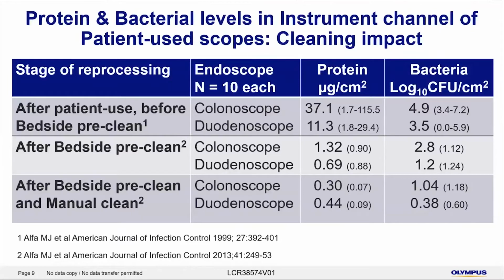What I'd like to point out is the second row, which is after the bedside pre-clean. In all instances, you're getting over 94% reduction in the protein levels, and you're getting at least a 2 log reduction in the microbial levels. So you can see that it's an ideal opportunity to get rid of most of the contaminating material that's present in an endoscope. And you can see on the bottom row that after the bedside pre-clean and the manual clean, done on another set of 10 patient-used endoscopes, the level of protein goes down even lower and the bacterial levels also are decreased.